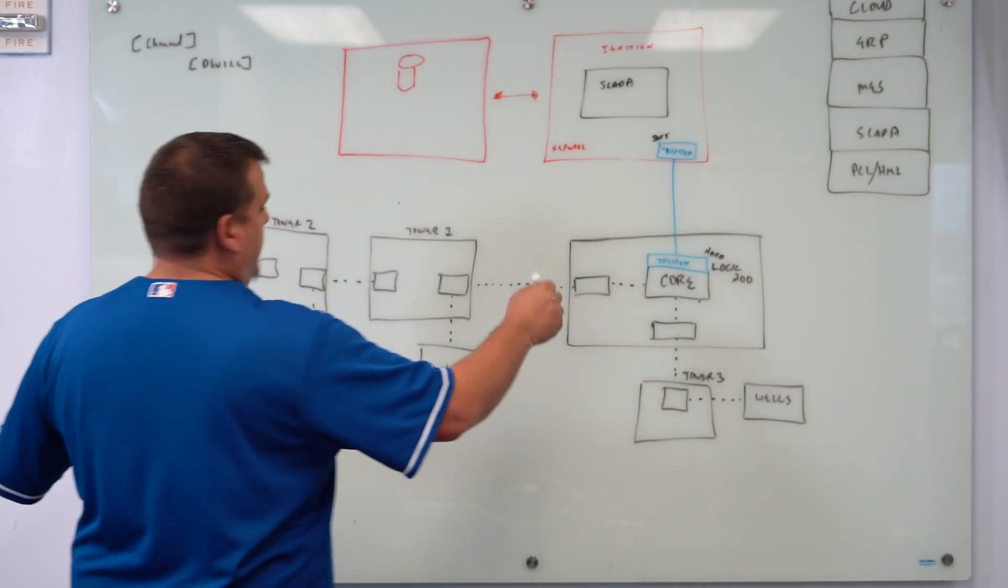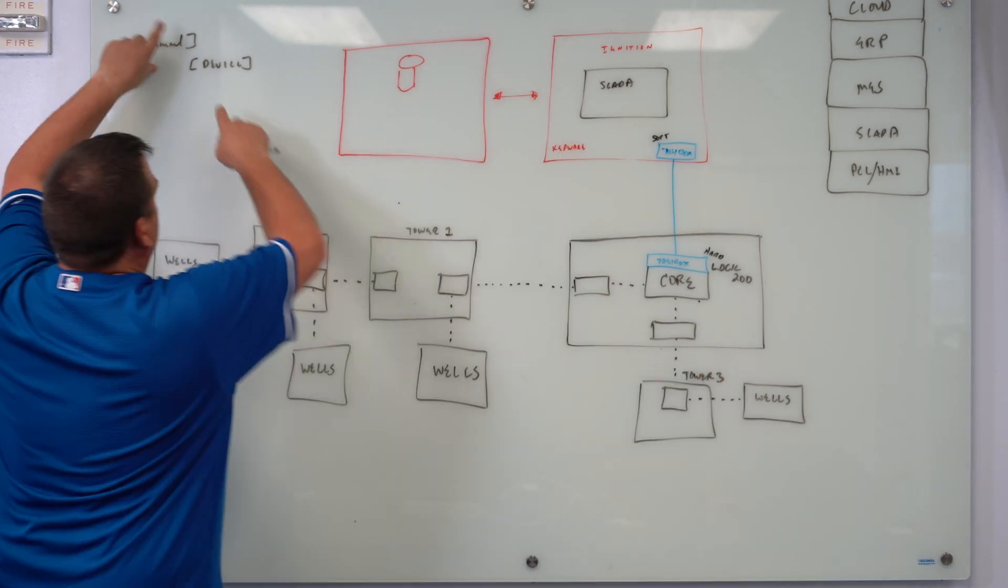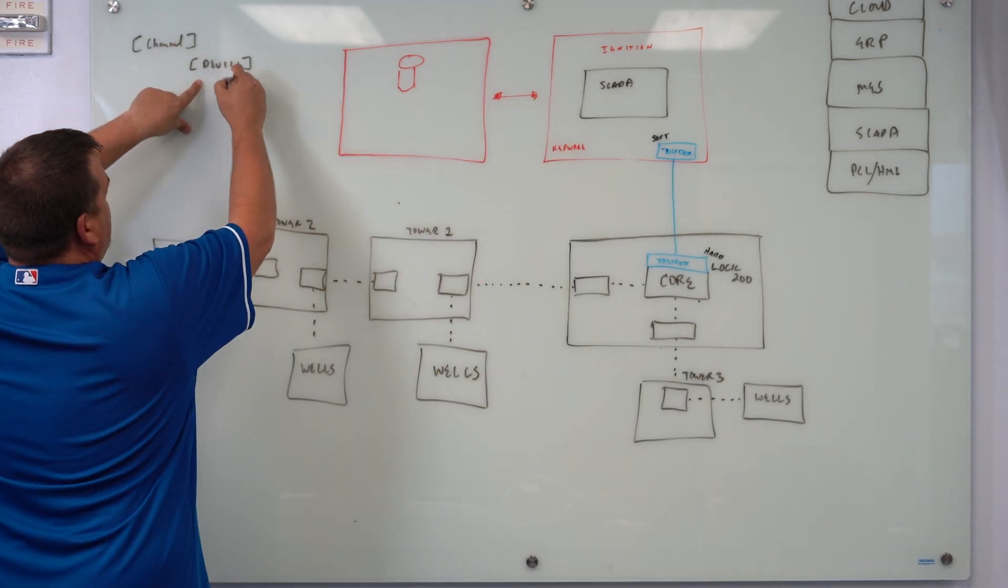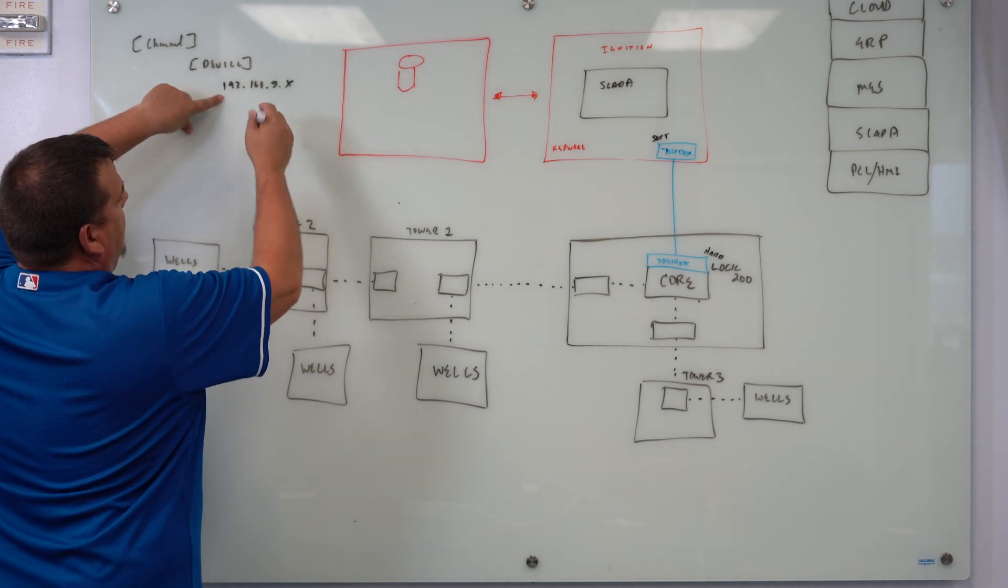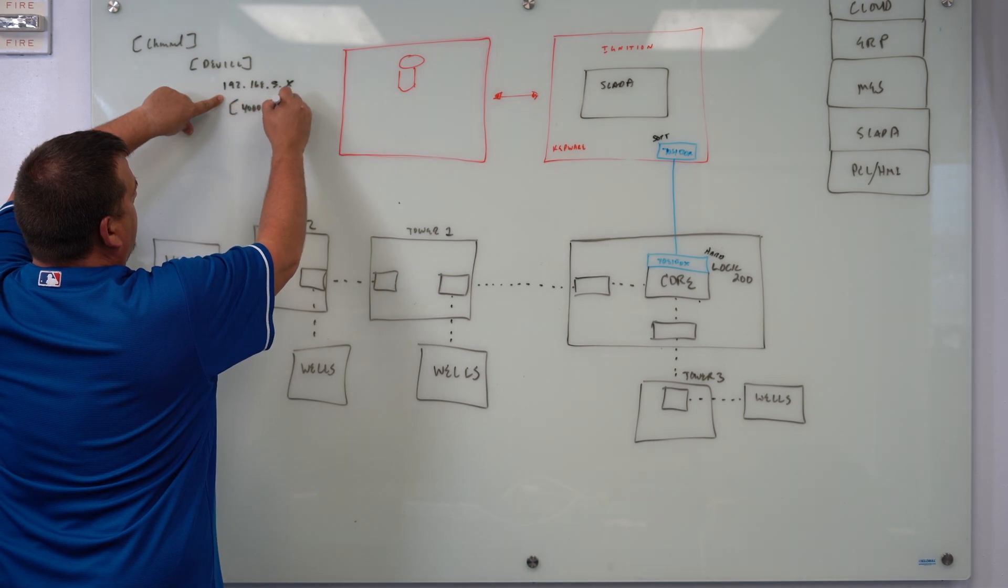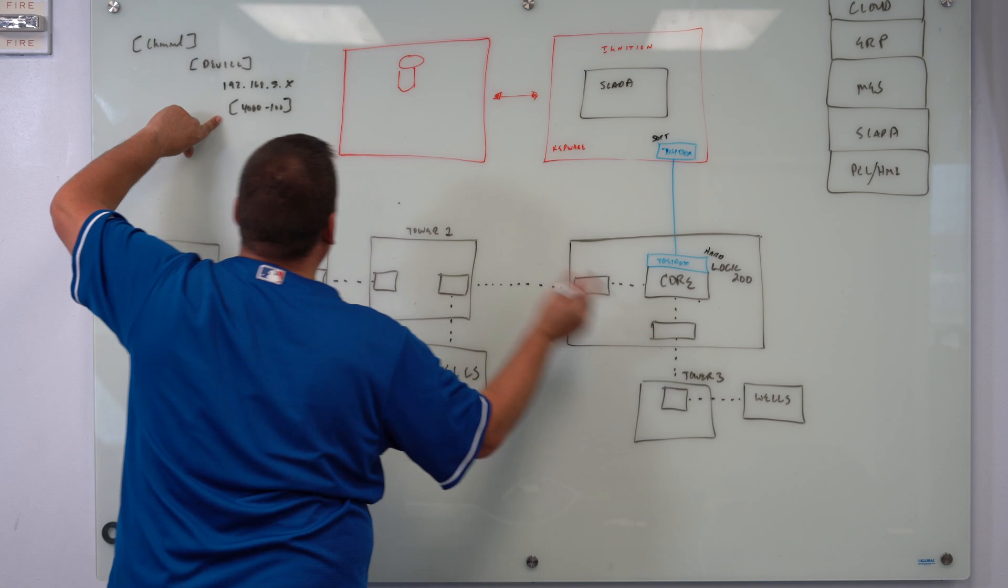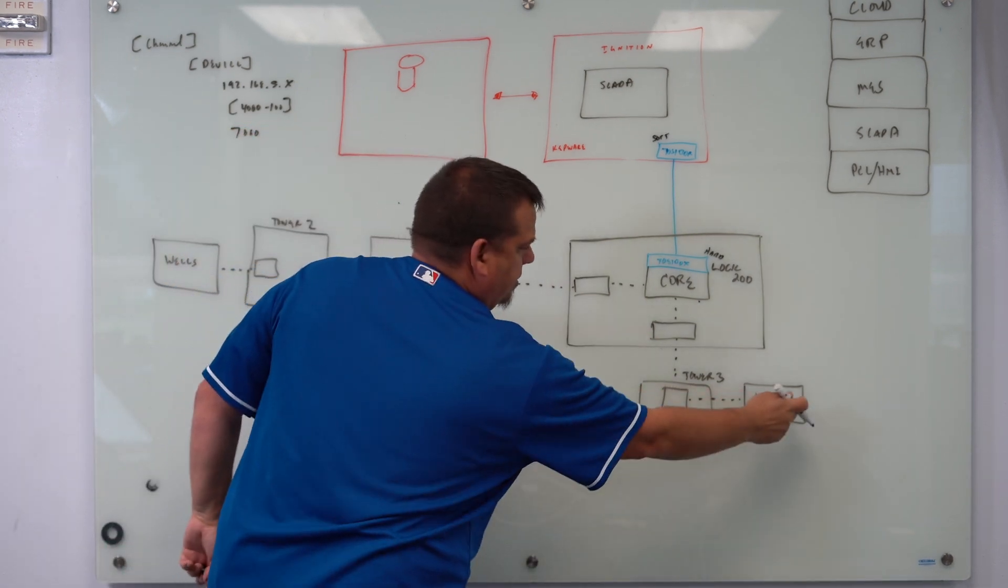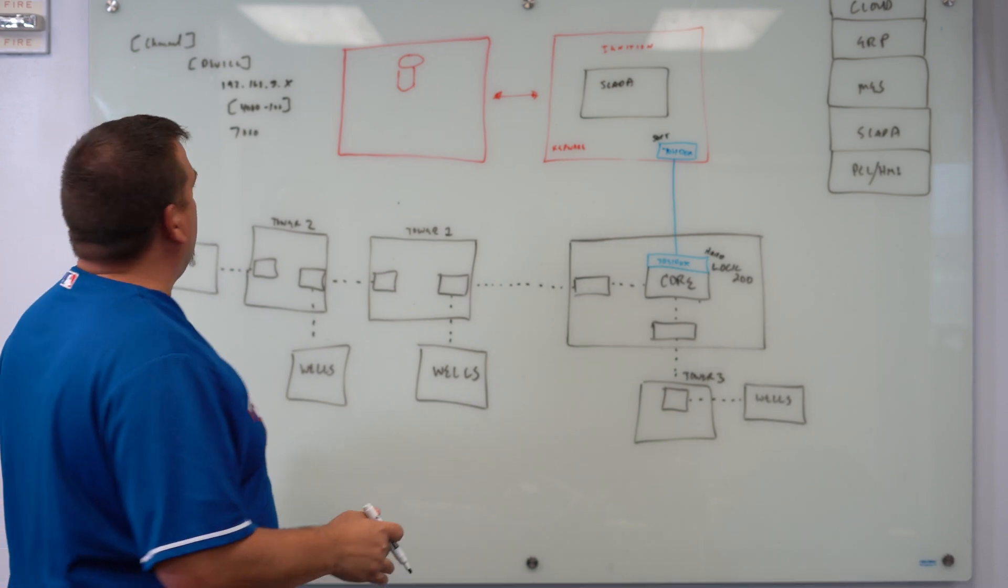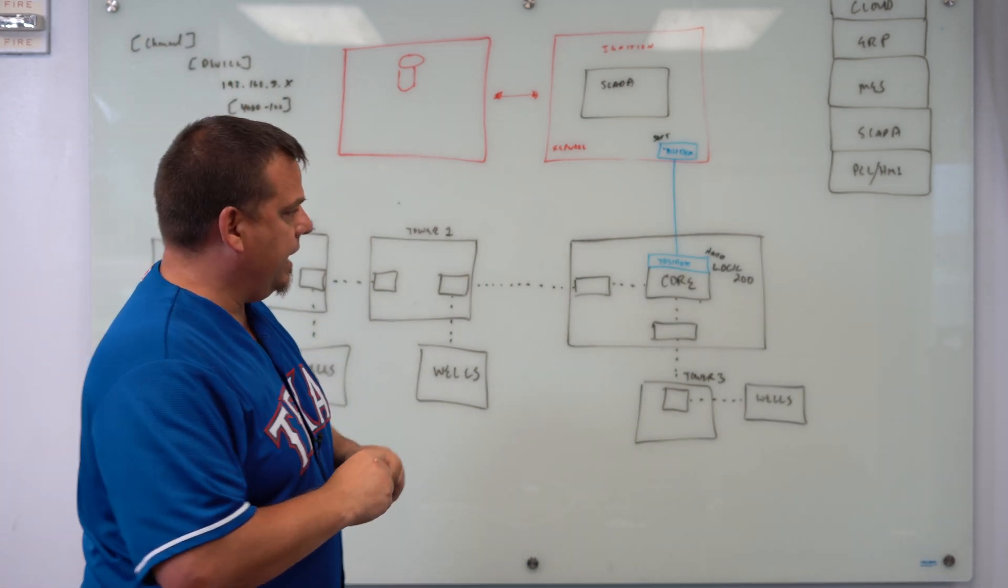The way that we talk to each individual well, we have a channel which is the ABB total flow driver. Then we have a device for each well. In that device, we have an IP address which would get us out to our radio, and then there's a meter ID. In this case, let's say it's 4000-100. There's also a port. We have to tell it which port on the master radio - let's say it's 7000 - is going to get us to the serial communications. When you've got 550 wells, there's a lot of configuration you do to be able to talk to all those wells.